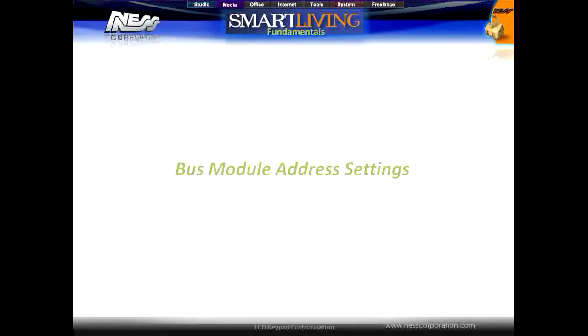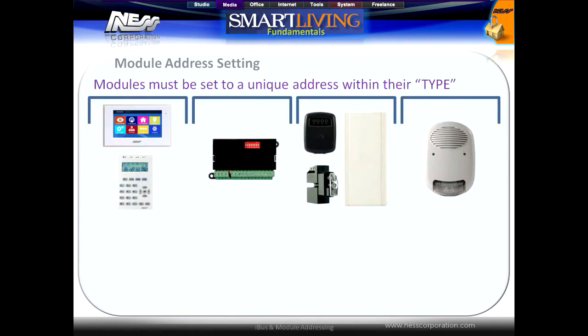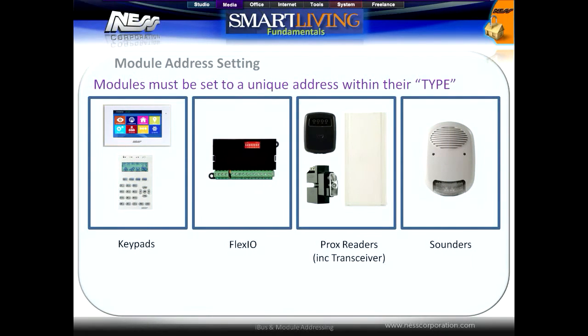Now we're going to have a look at configuring data bus module addresses. Each module on the data bus needs a unique address within its module type. Keypads are one type, the Flex module is another type, prox readers are another type — and this includes the transceiver, which is considered a wireless proximity reader — and sounders are the final type.